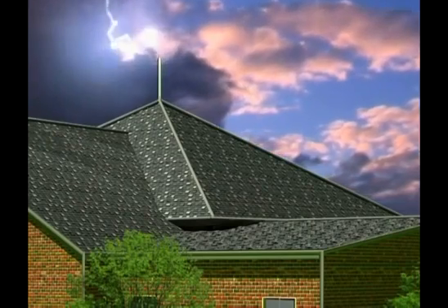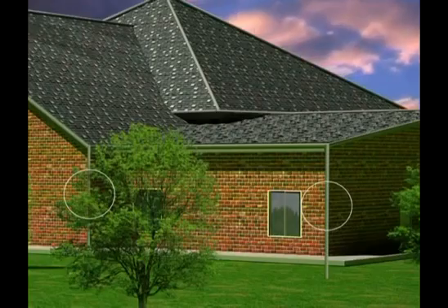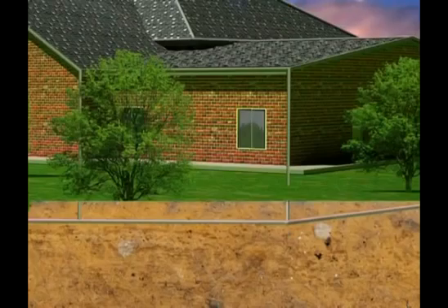Apart from the air terminal, the down conductor is the most important component of the external protection system. The down conductor's function is to channel the electric charge captured by the air terminal to the earthing system. The down conductors are to be installed in a manner so as to enable the smooth flow of electricity speedily and efficiently to the earth. In buildings with complex shapes, all shapes and edges of the building are to be protected and connected to the down conductor and the earthing system.